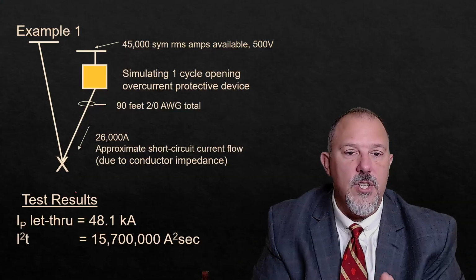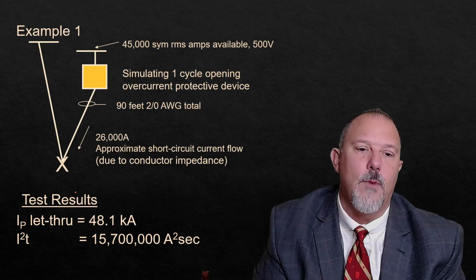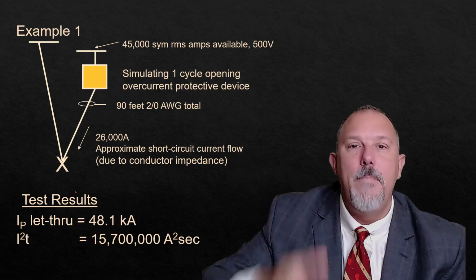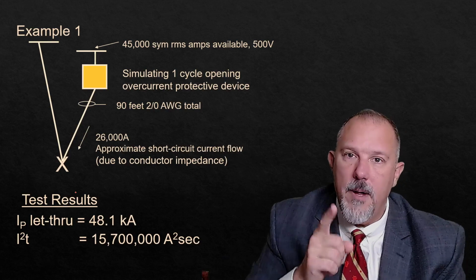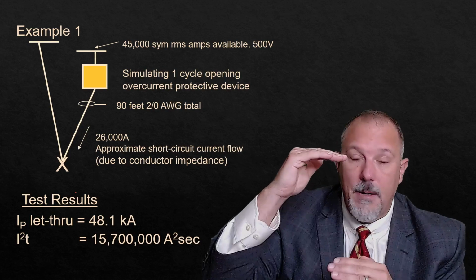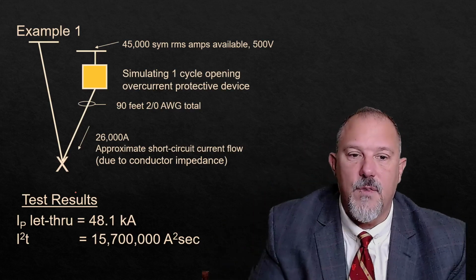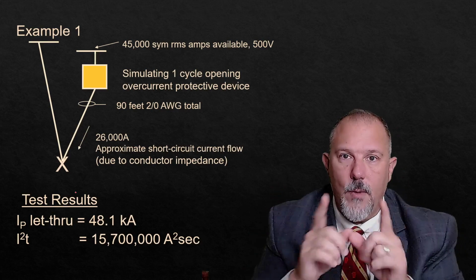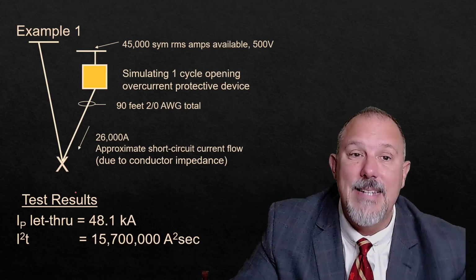Think about having a circuit breaker upstream that can let 30 cycles of current of up to 100,000 amps through, or 90,000 amps, or 45,000 amps. This is 26,000 amps for one cycle, 0.016 seconds. What we saw was a peak current of 48,100 amps, 15.7 million amps squared seconds. That's the heat. Remember, the magnetic forces come from that peak current, that rate of change from here to here, and the heat comes from the amps squared seconds, how much time I let flow, and we let one cycle flow.